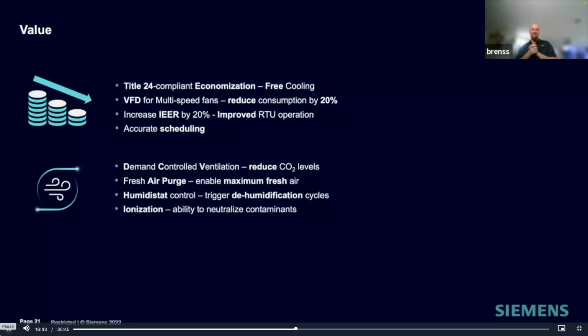Demand-controlled ventilation, reducing CO2 levels. Again, with the fresh air purge, this could be done from a schedule. This could be done from a push button on the mobile app. It could be done at any time to just cycle the air before a wedding, cycle the air in retirement communities, always making sure that the air is as fresh as can be. We have humidistat control. We can trigger dehumidification cycles anytime we like. Ionization is now built into our controller, the ability to neutralize contaminants in the air.